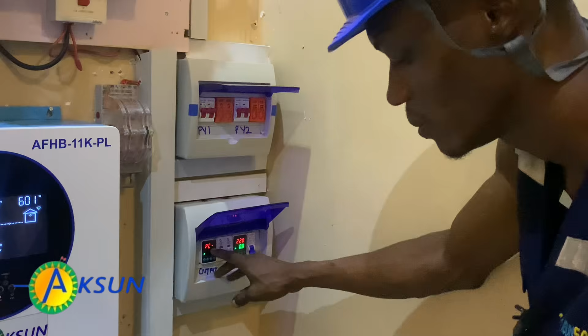And then we have arms now. Now this is the main place. What is our inverter KVA? 11 kVA, that is 11,000. I will remove my power factor. I like using 0.9, though for every big inverter they must design the system to a power factor of 1. But I don't like going with maximum. I don't like building my inverter to maximum. So let's use 0.9. That is 9,900 watts.